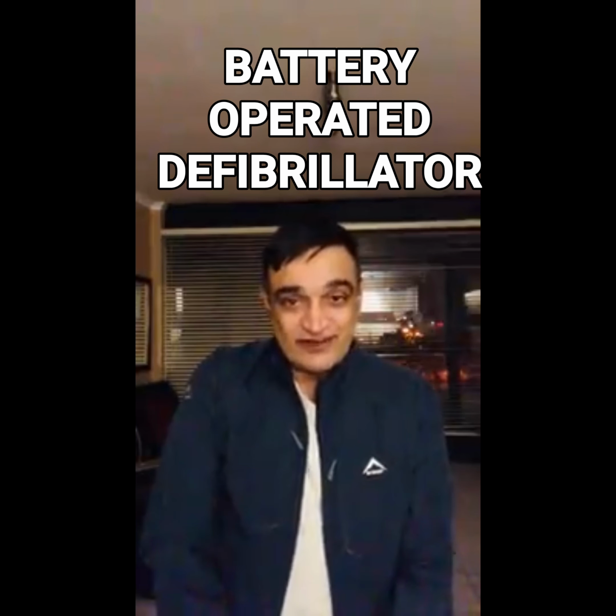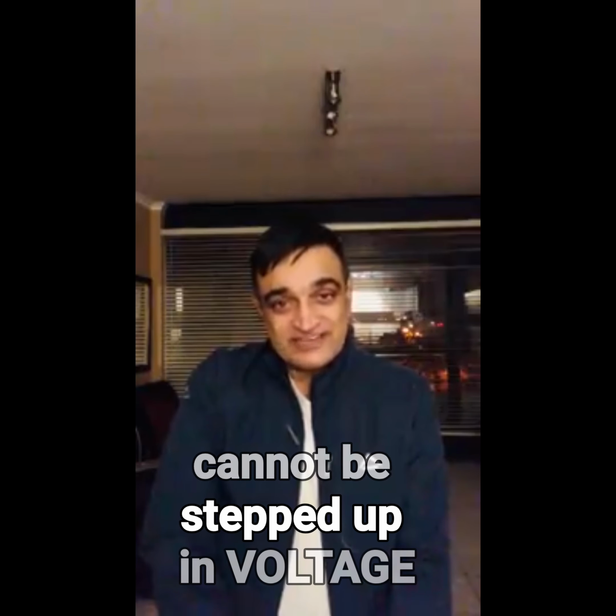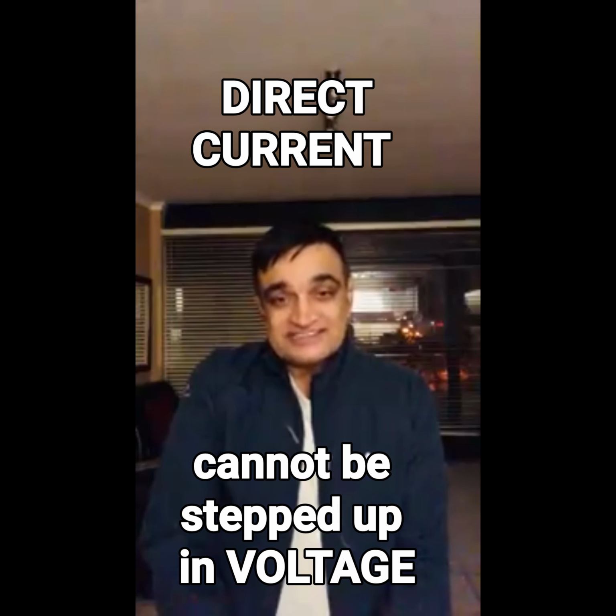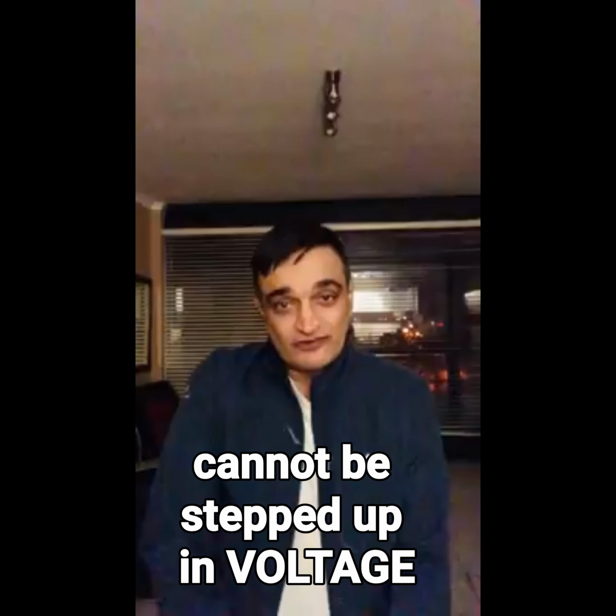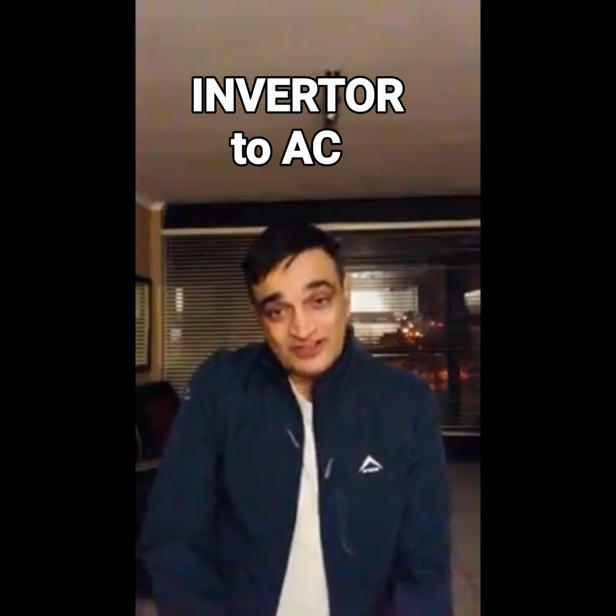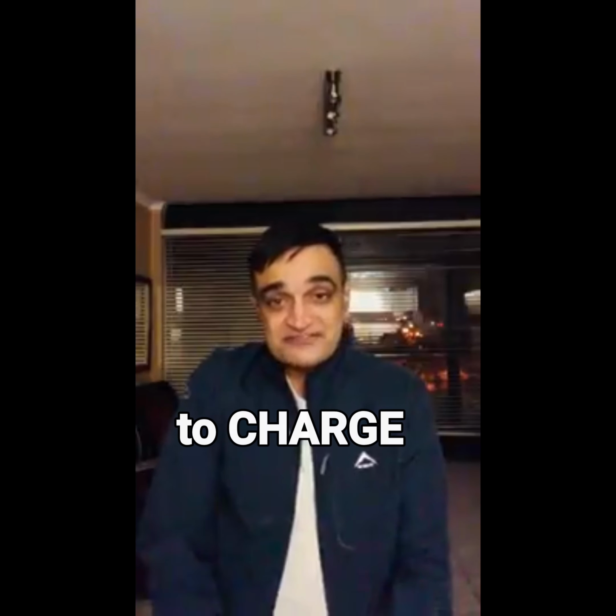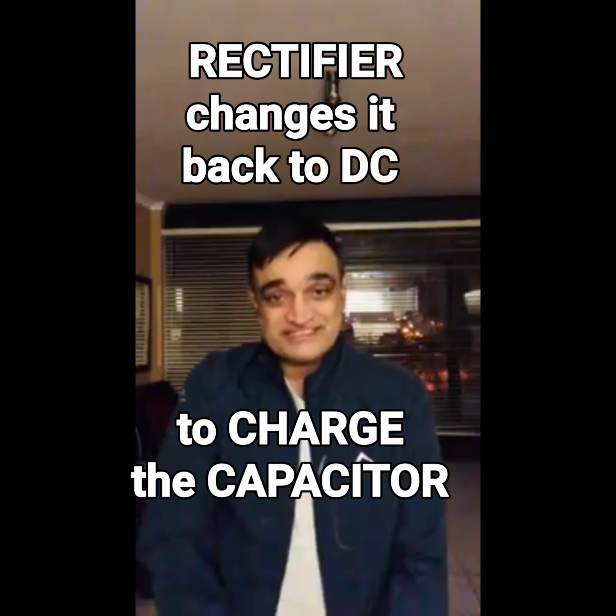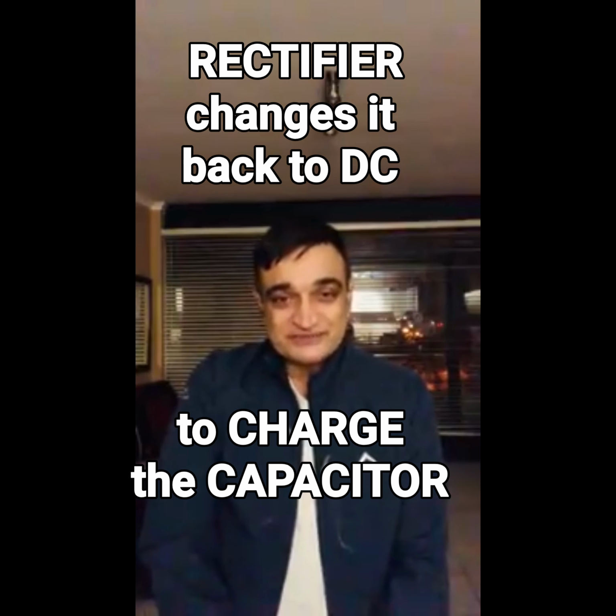Now the question comes, what happens with a battery operated device? Now, battery operated devices use direct current, but the thing is, direct current cannot be stepped up in voltage. You need to step up that voltage so that the transformer can increase it to 5,000 volts. So what happens is that direct current is converted by an inverter to alternating current, which is then used to step up the voltage to 5,000 volts, and thereafter it gets rectified to direct current to charge the capacitor. So that's how a battery operated device works.